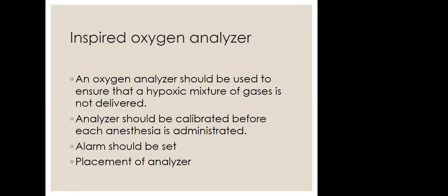For the inspired gas analyzer, it should be used to ensure that a hypoxic mixture of gases is not delivered. The analyzer should be calibrated before each anesthesia is administered, and an alarm should be set so that we can make sure there is no delivery of the hypoxic gas mixture. The analyzer should be calibrated for air, 21% oxygen, and 100% oxygen. It should read at least 21% before every anesthetic is administered.